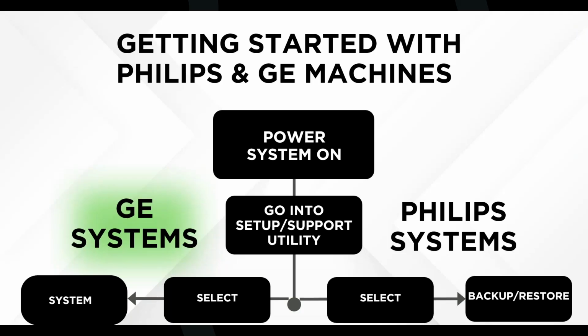On the left-hand side here, backup restore. I typically use thumb drives when I'm backing up. Come over here, select the drive, and then back up. Now this will go on the Philips system here. It gives you a list of the things that it's backing up. And we were talking about the 3 keys that we wanted to make sure that we had backed up.